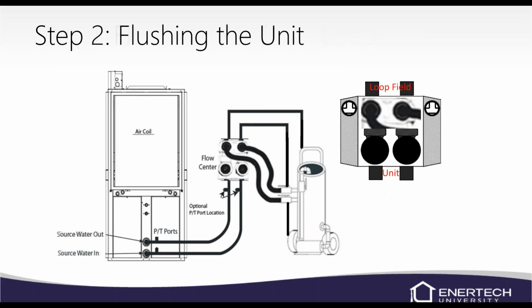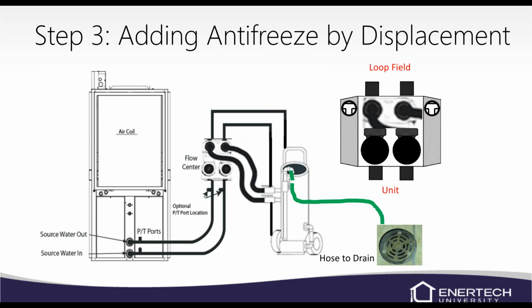After you flush the loop field, then you're going to switch over your three-way valves and flush just the unit, and it won't take very long to flush the unit, maybe 10, 15 minutes max. After you've flushed the unit, then you'll want to go ahead and add antifreeze to the system.